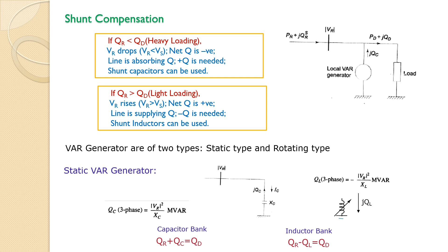In case of off-peak or light loading conditions, the reactive power demand is less than the reactive power supplied. That is, QR is more than QD. In such a situation, the voltage at the receiving end will increase. That is, VR will be greater than VS. And if we calculate the net Q, it will be positive. It means the line is actually supplying Q. So minus Q is required to meet the condition of balance between QR and QD. So in this case, shunt inductors are needed.